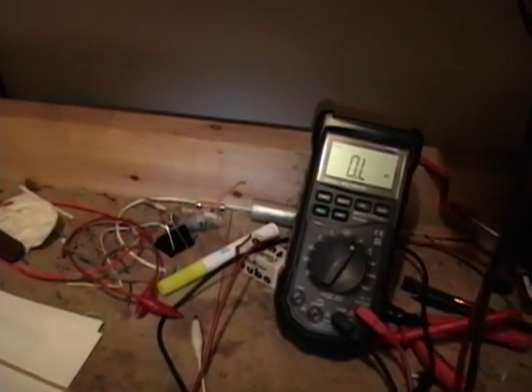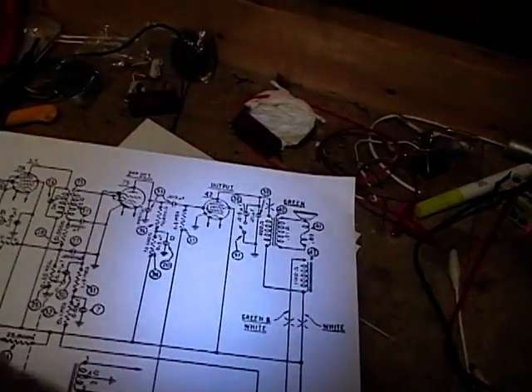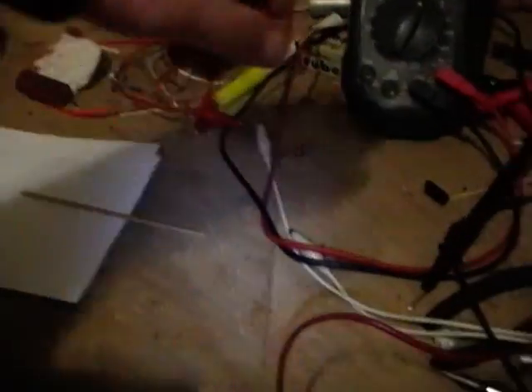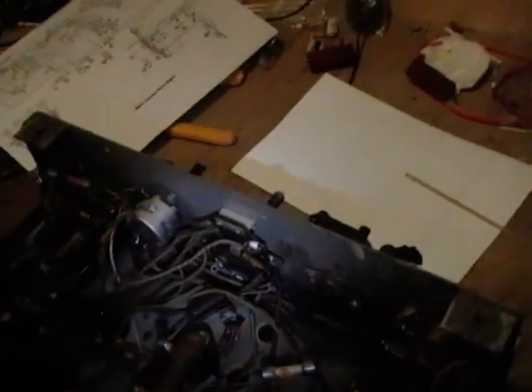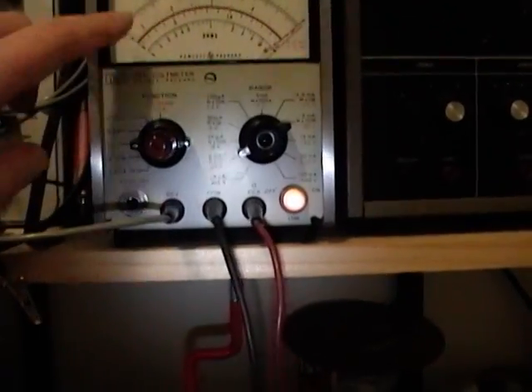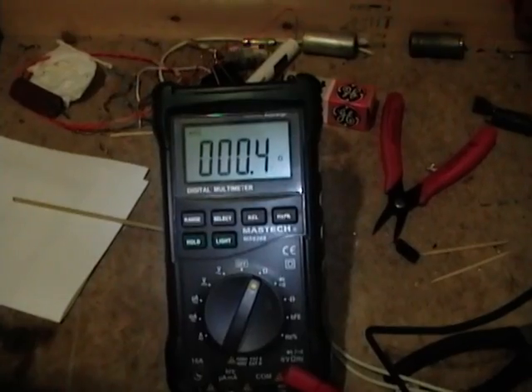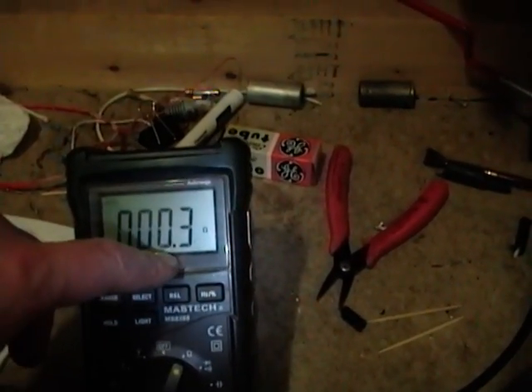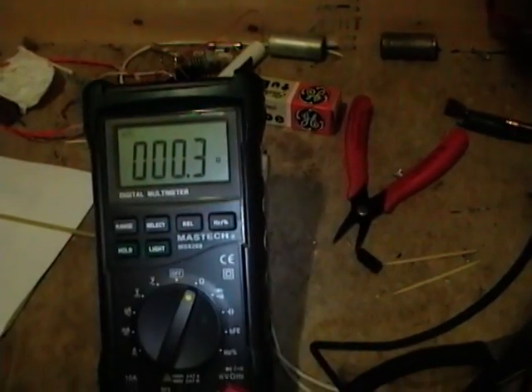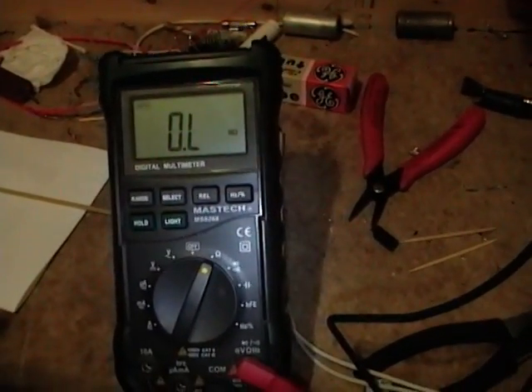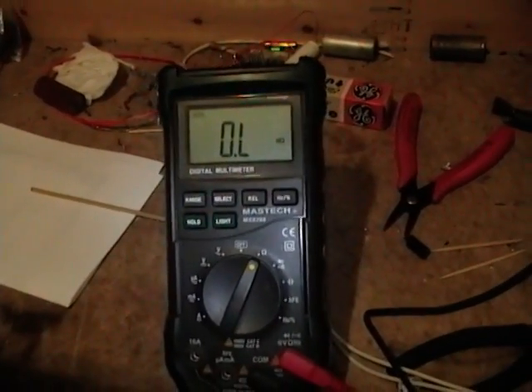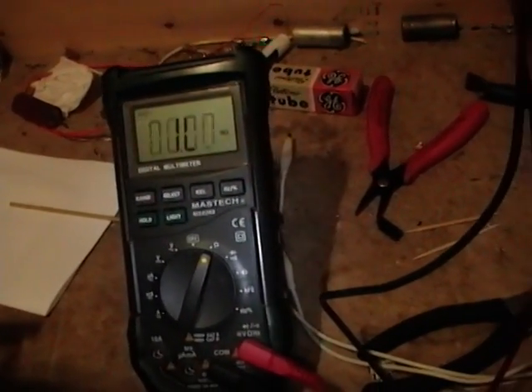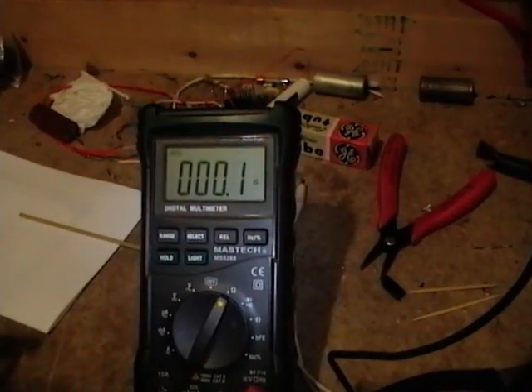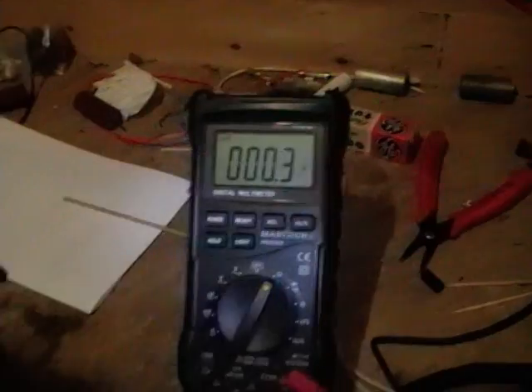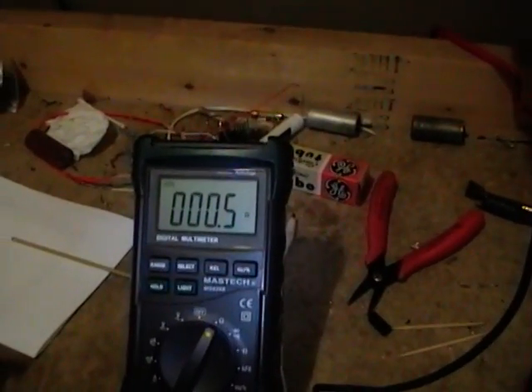So the 2 windings are reading lower by a factor of 10, but then again they do measure about the same between the two, so it might be okay. Maybe the meter's just off a bit on that, because that is really at the bottom end of this meter's range. This is also measuring really low, like 0.3 ohms. Well, I guess the only way to really find out is to try to actually power up the transformer. Yeah, same thing on the 80 rectifier, about 0.3, 0.4 ohms, 0.5.